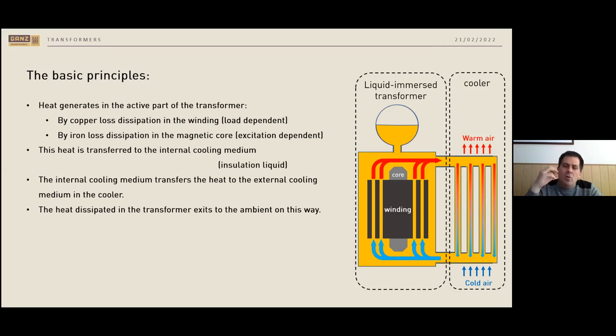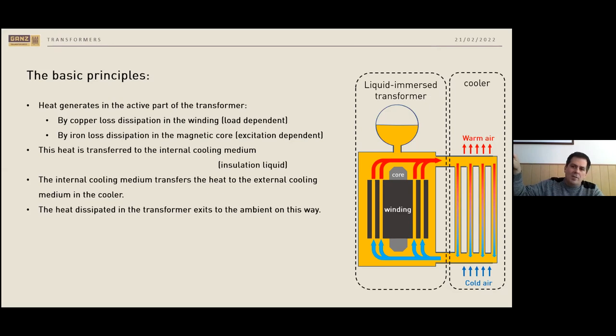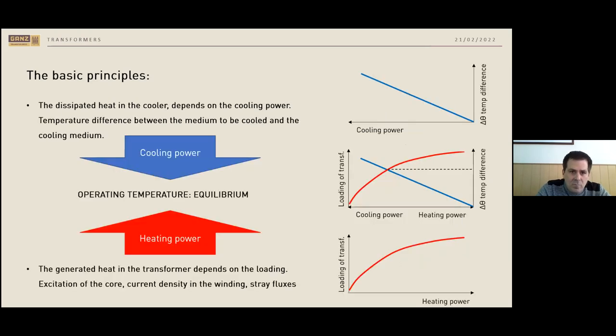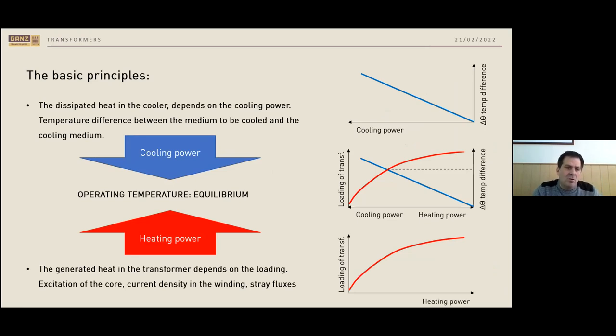This presentation is mainly restricted to liquid-immersed transformers. The primary cooling medium is the insulation oil, which circulates within the winding and through the cooler. Heat is transferred to the ambient air externally. Oil circulates because heating decreases oil density, so hotter oil rises; when it enters the cooler and cools down, its density increases and it descends due to gravity, creating natural circulation in the transformer.